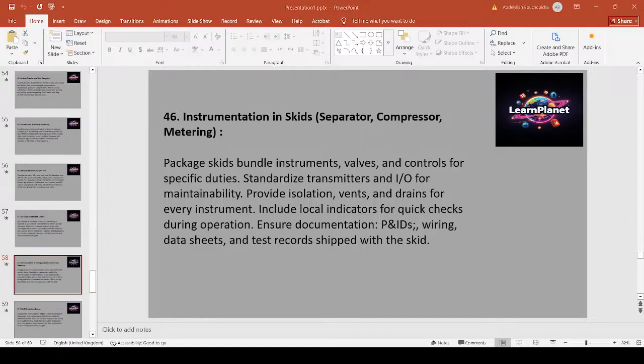Skid centralized instruments, valves, and controls for modularity and quicker commissioning. Standardized transmitters and IOs to ease spares and maintenance. Provide accessible isolation, vents, drains, and local indicators to speed troubleshooting. Ship complete documentation, P&IDs, wiring, datasheets, and test records with the skid, and ensure traceability of components. Example: a compressor skid includes local pressure indicators, redundant transmitters, and pre-wired marshalling to simplify on-site hookup and SIT.